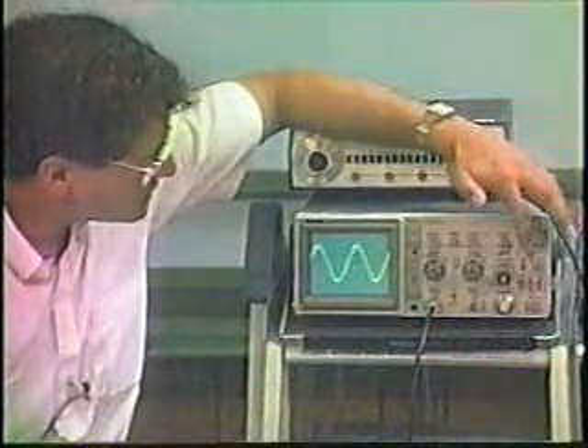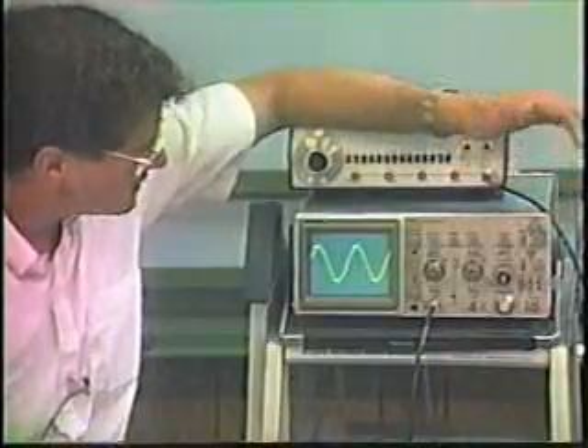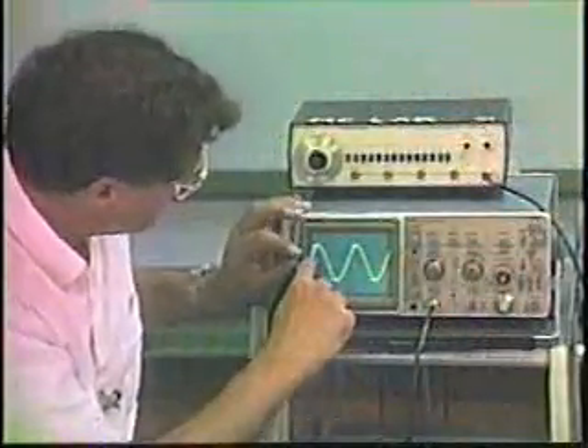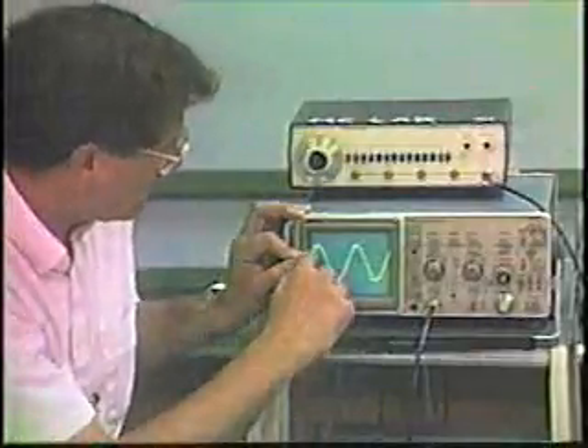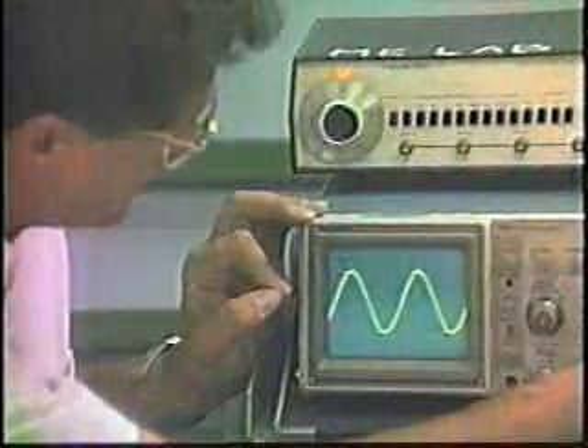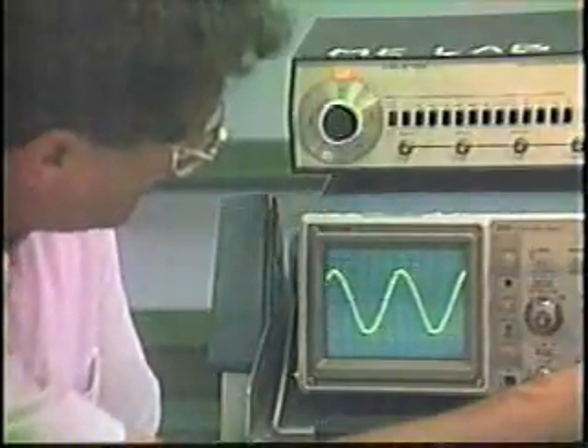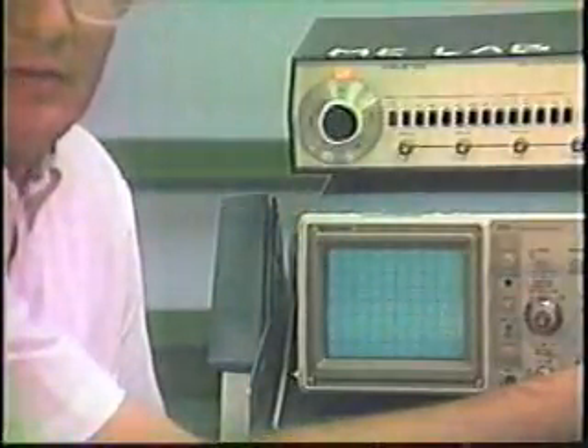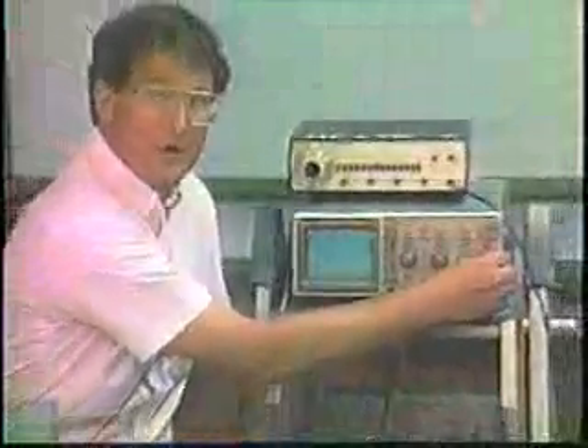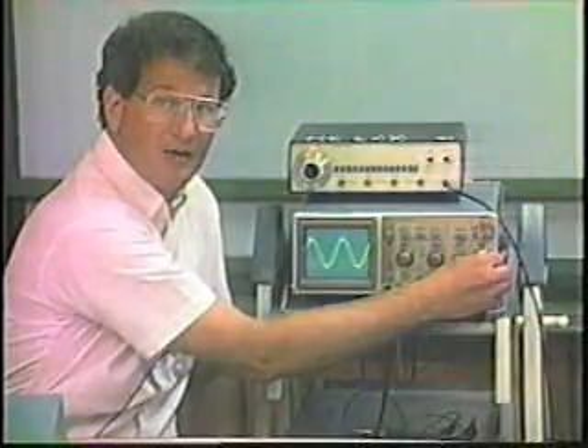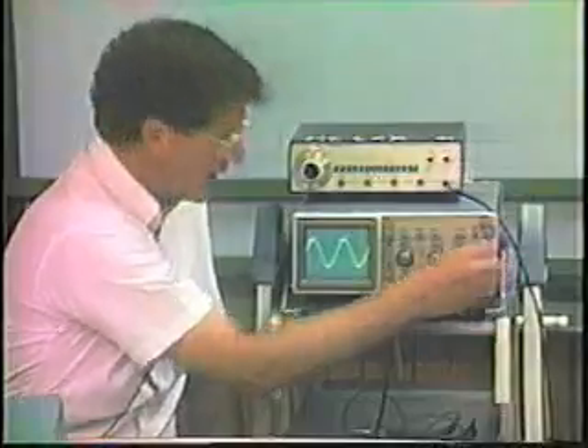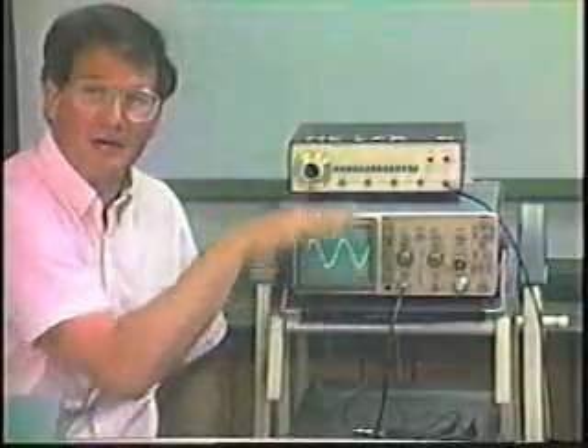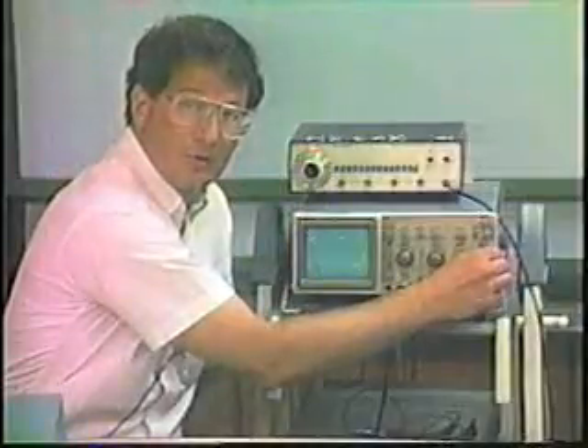The final feature of the oscilloscope concerning the trigger is the level. You'll notice that I've begun the sweep at a level somewhat above 0. I can vary that simply by changing the level. Now notice if I set the level too high, I'm beyond the level of the signal, and the signal disappears from the oscilloscope. When I bring the level down to the maximum value, then I have a sweep. If I bring it down further, then I'm down to 0, the lowest value, and if I go beyond that, it disappears. So I can use this to trigger or initiate this display at any level within that signal, and that's what the level control allows you to do.